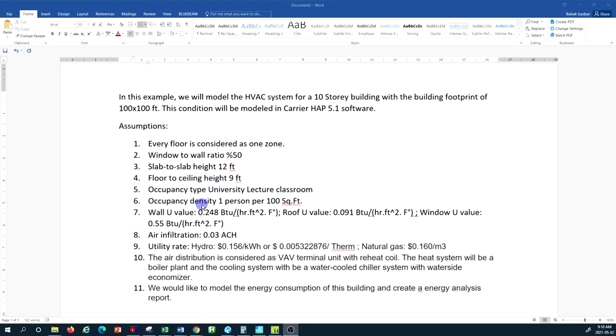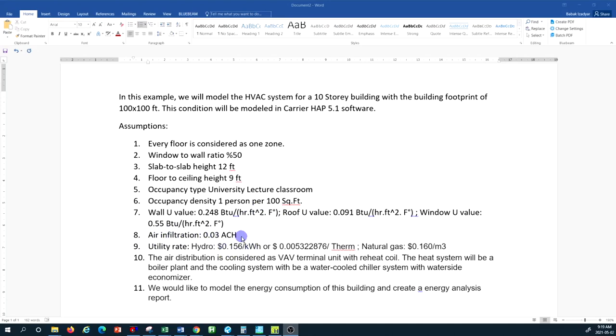The occupancy density is one person per 100 square feet. We have assumed U-values for the wall, roof, and windows. The wall U-value is 0.248, the window U-value is 0.55, and the air infiltration — air coming into the building unwanted from the building envelope, specifically from windows and doors — is assumed to be 0.03 air change per hour.